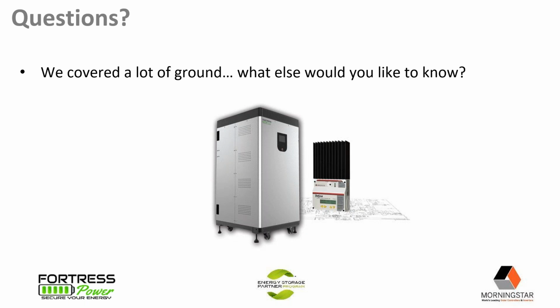How would a Fortress lithium battery perform in areas with 100% humidity with condensation? It's a good question, there are a lot of places like the islands or Latin America and South America where that's a reality. What I would recommend is to take a look at the EFlex. That enclosure is IP65 rated, so it does a very good job resisting moisture and humidity in those kinds of areas. If you're looking at the eVault in one of those areas, there are a lot of different enclosure companies that can make a NEMA 3R rated enclosure, or similarly rated, to protect it against high humidity, salt, or moisture. There are a lot of creative ways to do this. With the EFlex, it's pretty much covered with the enclosure, but with the eVault, we may want to look at other enclosure options, just to be safe rather than sorry.